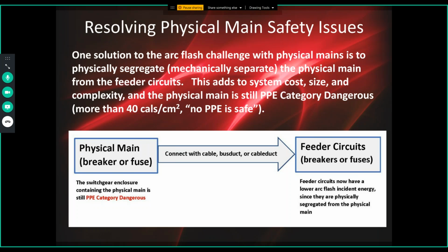But I would argue, if you can't do a secondary virtual main because the utility owns the transformer, physically segregating the secondary main breaker from the feeder circuits is the next best solution. Not as good as a secondary virtual main, takes up space, costs a lot of money, still at PPE category dangerous, but it is still better than close coupling those two pieces of equipment in terms of electrical safety and maintainability.